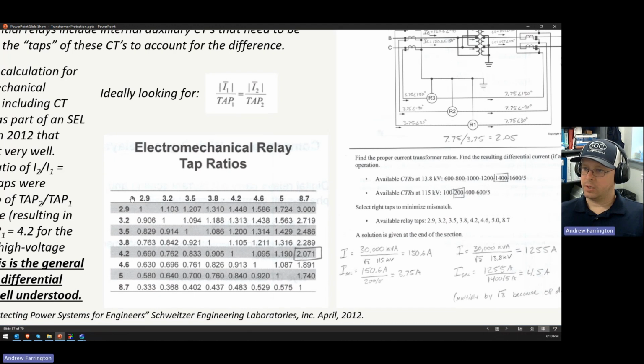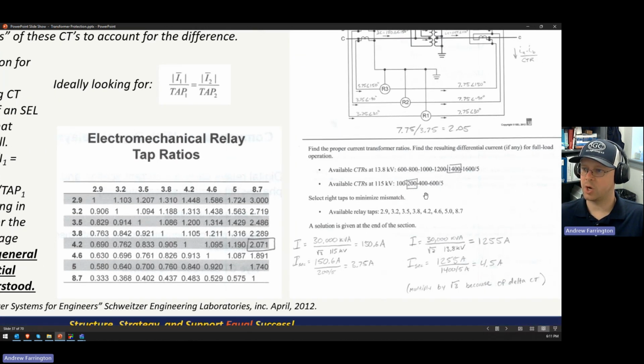This table is, these are the different taps that are available for this particular relay. So there are 8 taps available for tap 2, and then this is tap 1. And this table gives you the ratio of tap 2 to tap 1. So obviously 2.9 divided by 2.9 is 1. And what you're trying to do is find a ratio on the table that is as close as possible to the ratio that you calculated. This will give you the minimum amount of mismatch and the lowest error in the current seen by the relay, so that you can get that differential operate current to a minimum.